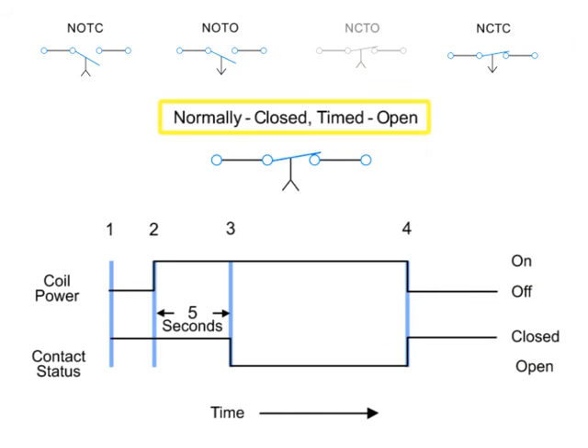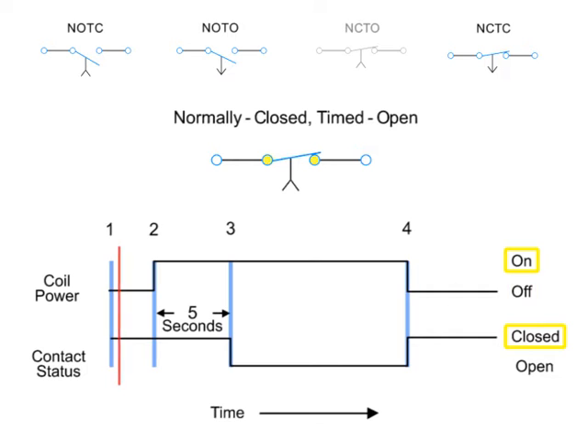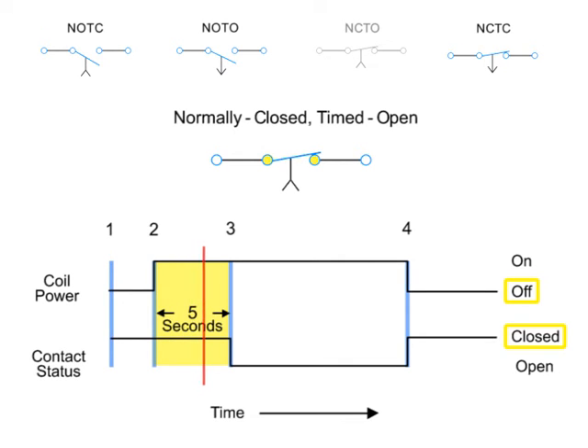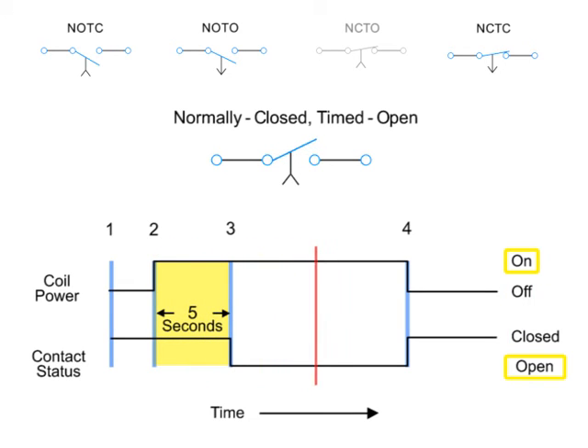Next, we have the normally closed, timed open contact. This type of contact is normally closed when the coil is unpowered or de-energized. The contact is opened with the application of power to the relay coil, but only after the coil has been continuously powered for the specified amount of time — in this case five seconds. Thus, the contacts open five seconds after the coil is energized and close immediately when the coil is de-energized.